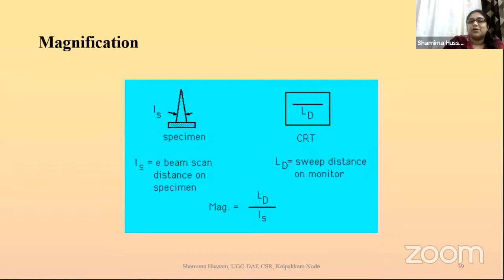However, if you scan 10 nanometers of the area and project it across a bigger 1 mm size, then the magnification would be 1 mm by 10 nanometers. So 10 to the power minus 3 meters by 10 to the power minus 9 meters, which is a magnification of about 10 to the power 6. This is how we define magnification, right? This is how it looks.